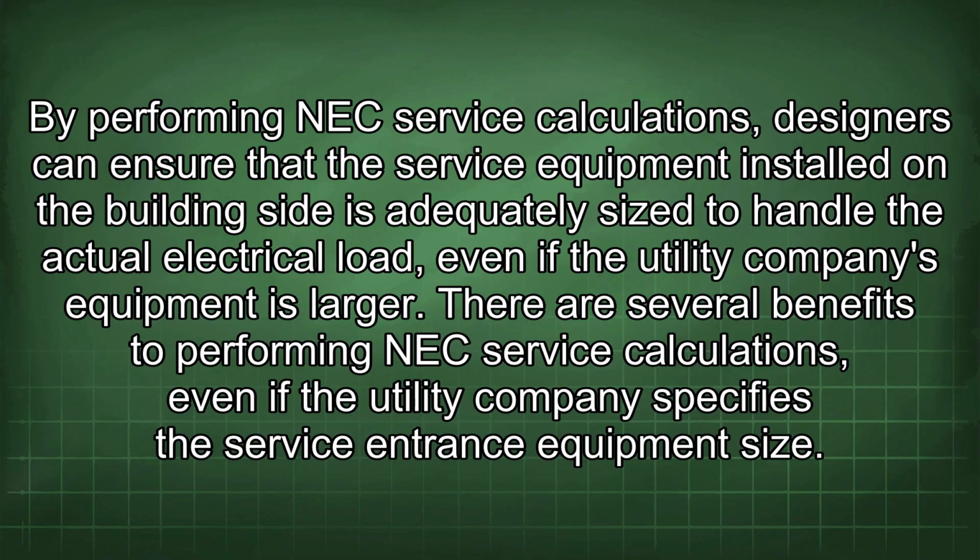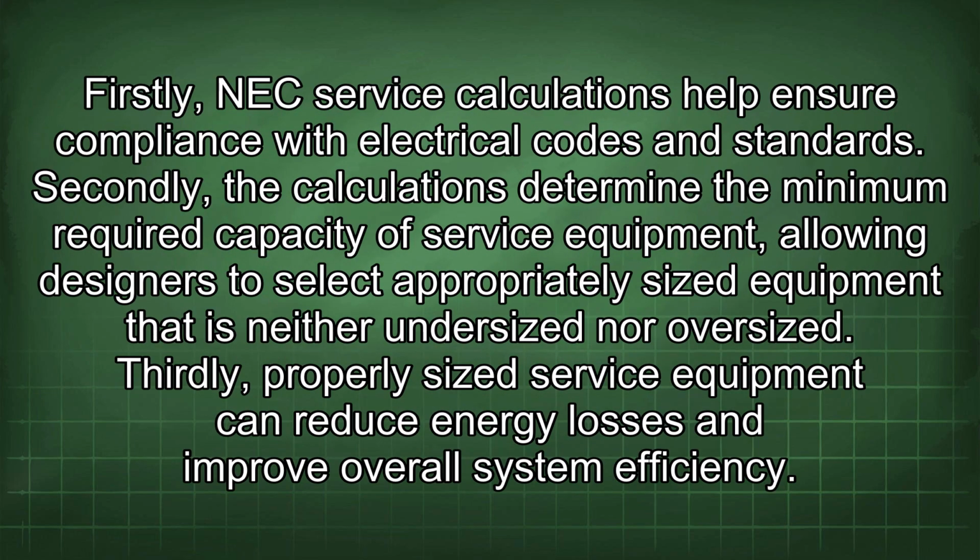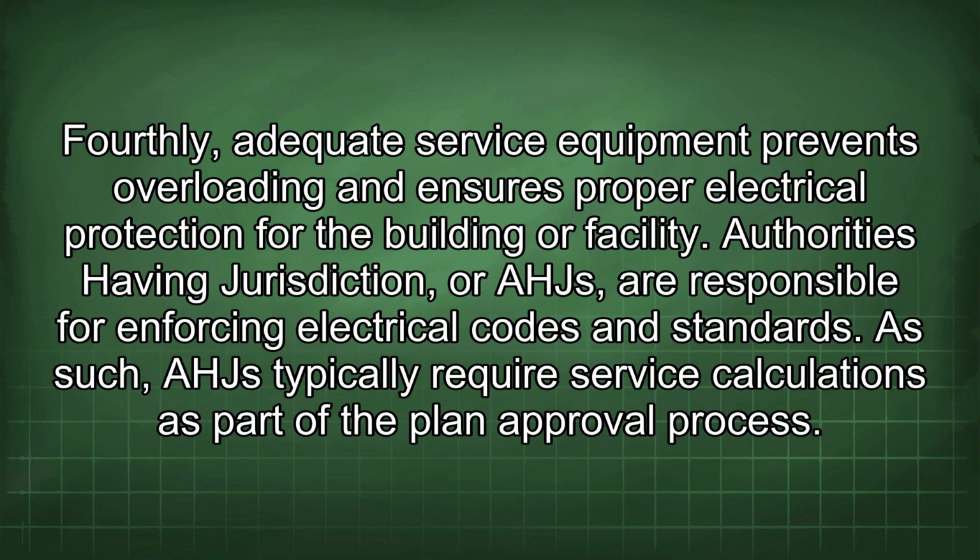There are several benefits to performing NEC service calculations, even if the utility company specifies the service entrance equipment size. Firstly, NEC service calculations help ensure compliance with electrical codes and standards. Secondly, the calculations determine the minimum required capacity of service equipment, allowing designers to select appropriately sized equipment that is neither undersized nor oversized. Thirdly, properly sized service equipment can reduce energy losses and improve overall system efficiency. Fourthly, adequate service equipment prevents overloading and ensures proper electrical protection for the building or facility.